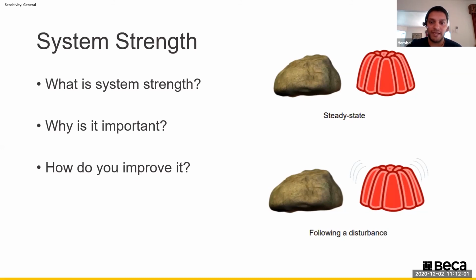Conversely, a weak system behaves like a jelly that wobbles when prodded. The wobbling is felt throughout the jelly, not just at the point of contact. Voltage is highly sensitive to any network disturbance, and depending on how many generators respond to the initial disturbance, this can create additional disturbances, leading to a snowball effect where voltage distortion increases to such a state that generators start to trip, creating further disturbances and leading to a worst case scenario: a system blackout. As we transition from large synchronous machine-based generation to inverter-based technology, system strength is becoming an increasingly important consideration.